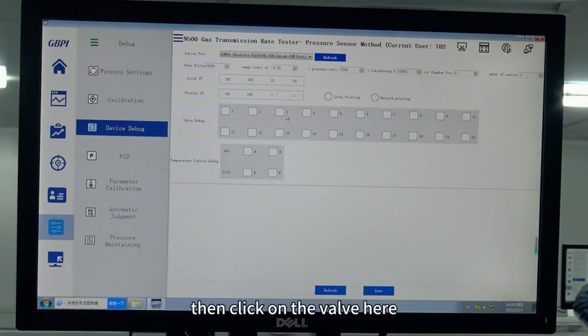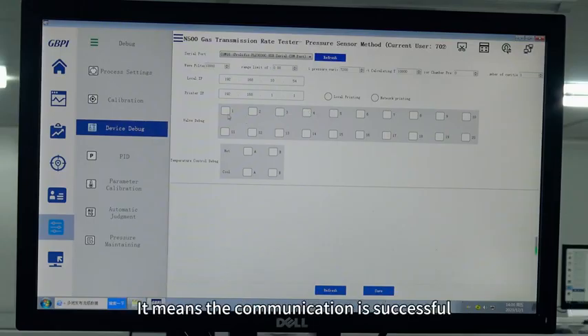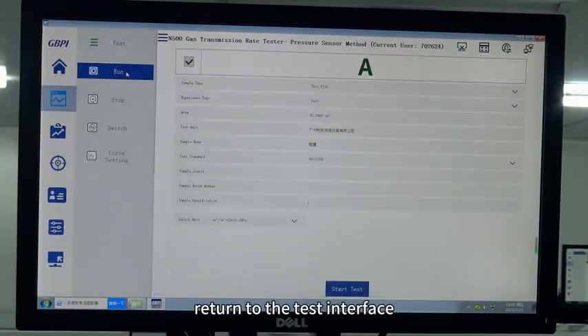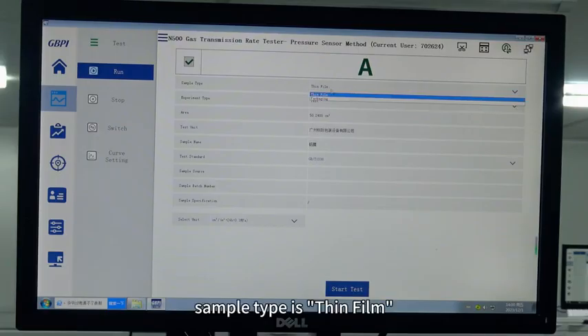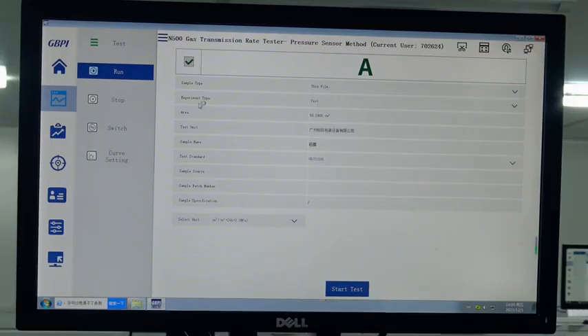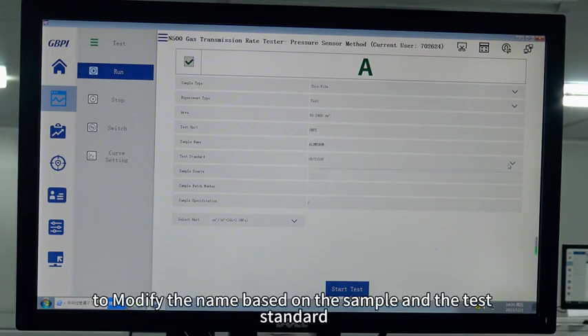Then click on the valve here. If you can hear the sound from the instrument, it means the communication is successful. Return to the test interface. Sample type is thin film. Experiment type is test. And the area is fixed at 50.24.